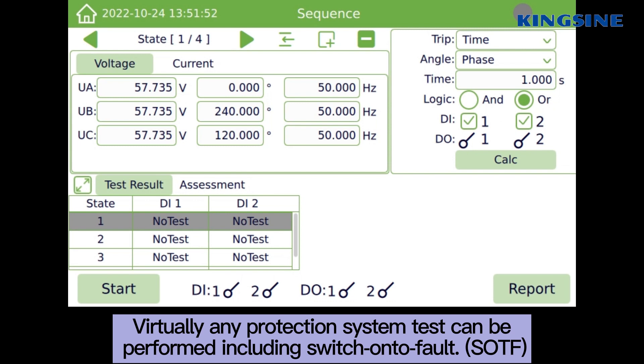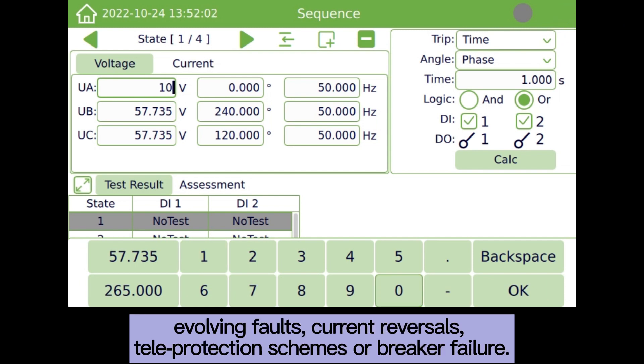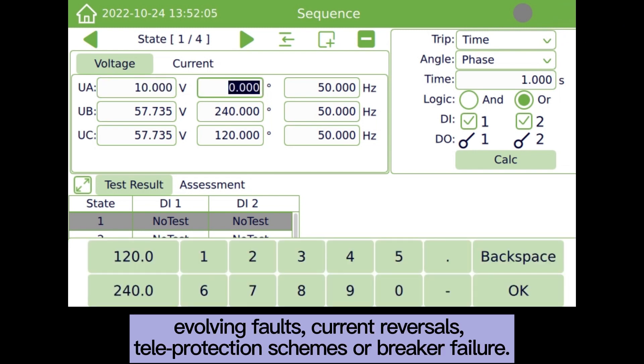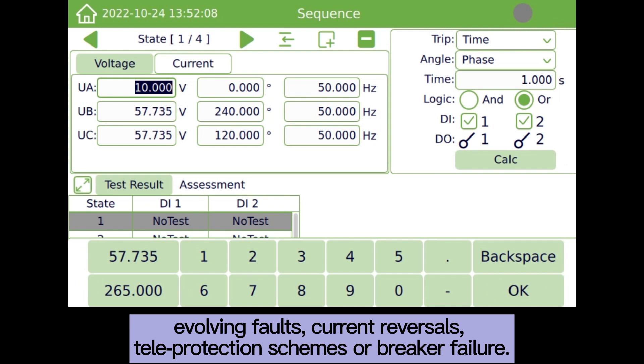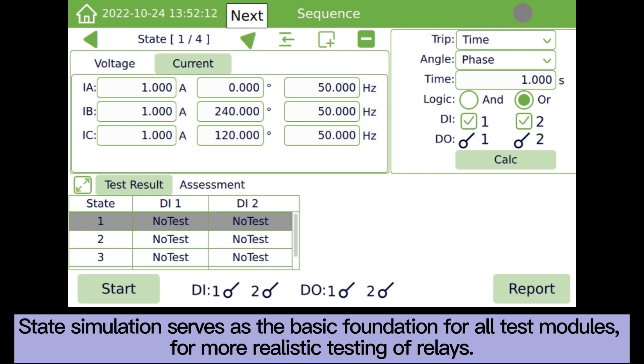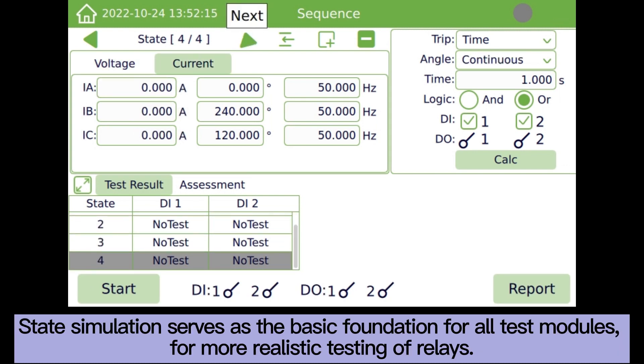Virtually any protection system test can be performed, including switch-on to fault, evolving faults, current reversals, teleprotection schemes, or breaker failure. State simulation serves as the basic foundation for all test modules.